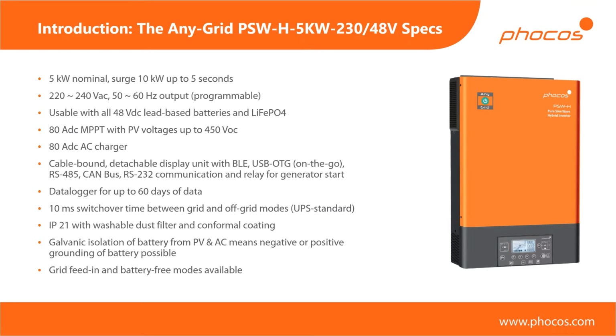We can use all types of 48 volt lead-based batteries, so gel batteries, AGM, liquid electrolyte, tubular, whatever, and lithium iron phosphate. You could theoretically also use other lithium chemistries, as long as your nominal voltage and your minimum and maximum voltage are within the limits of the inverter. If you look at the manual, for example, you'll also see that we have things like equalization charge to give the best possible treatment to your lead batteries, so that's something you would typically not require for lithium.